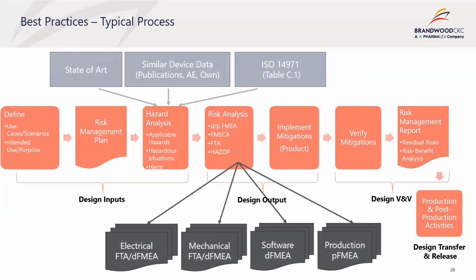It is recommended for complex devices to break down the risk analysis to engineering subsystems such as electrical, mechanical, or software, as typically different engineering teams would be responsible for each subsystem, and different approaches may be more suited. For example, fault tree analysis may be more suited for electrical subsystems, and design FMEA more suited for software. The mitigation should then be implemented in the design or product. The mitigations are then verified during the design V&V phases and should be traceable. The risk management report would then be completed prior to release, including the residual risks and any required risk-benefit analysis.